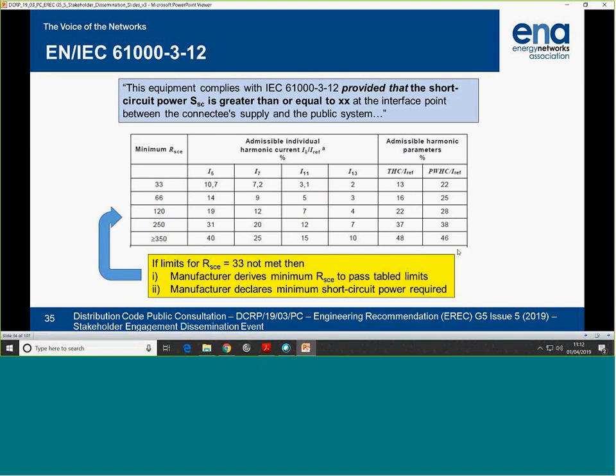And if it fails that, you're into the second of this table, where they have to state they require a short circuit fault level. So that is done. You can see the values, take the fifth harmonic, the values are going up. Your methodology amount is going up as you go down the column. And basically the strength of the system is going up, the R_sce is going up. If they were to interpolate, basically they've worked out what passes. They can then state that in their literature to everyone, to say what strength the supply is required.